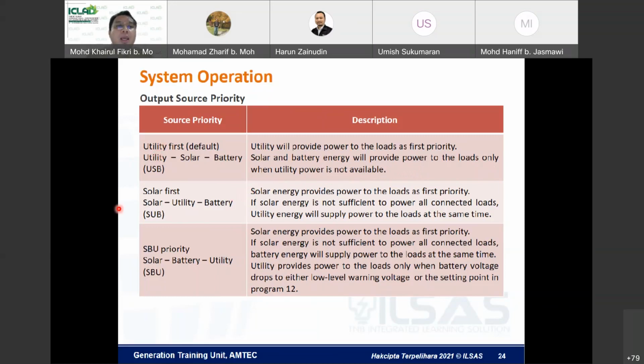This is the first mode, and the second mode is SUB - it's called Solar Utility and Battery. For this mode, the solar energy provides power to the load as first priority. If the solar energy is not sufficient to power all the connected loads, then the utility energy will supply power to the load at the same time.